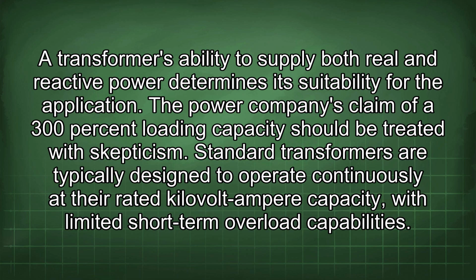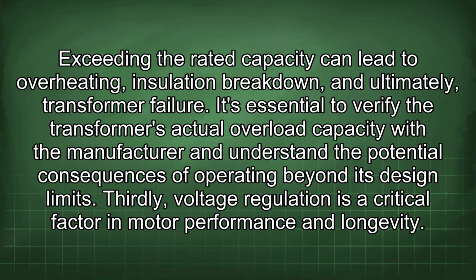The power company's claim of a 300% loading capacity should be treated with skepticism. Standard transformers are typically designed to operate continuously at their rated kilovolt ampere capacity, with limited short-term overload capabilities. Exceeding the rated capacity can lead to overheating, insulation breakdown, and ultimately transformer failure. It's essential to verify the transformer's actual overload capacity with the manufacturer and understand the potential consequences of operating beyond its design limits. Thirdly, voltage regulation is a critical factor in motor performance and longevity.